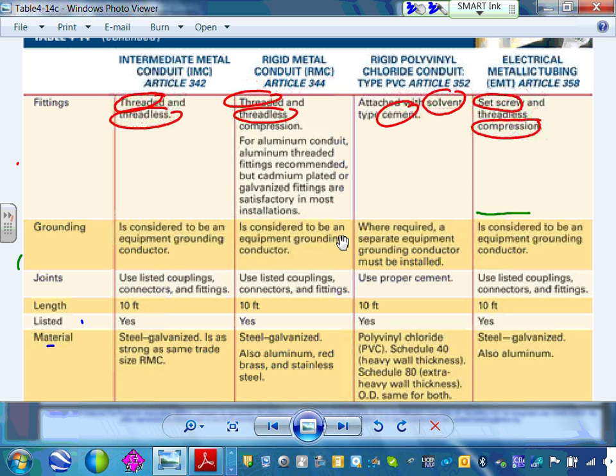Yes sir, is there a certain length they can't exceed for conduit? Like could that be a certain size, like they can't be 30 feet? The distance - yes, the only limitation on the distance is using it as an equipment ground conductor. Hold that question until we reach it. Yep, that's the only limitation. Can you pull them 500 feet, a solid one from here to there, or does it have to have a break so if something happens you can get into it?